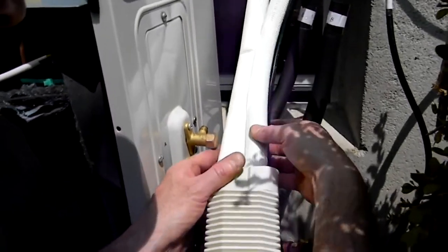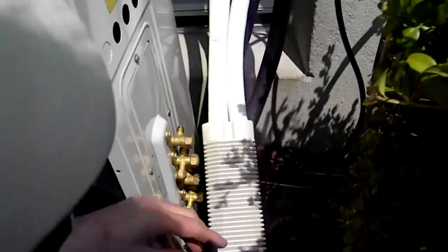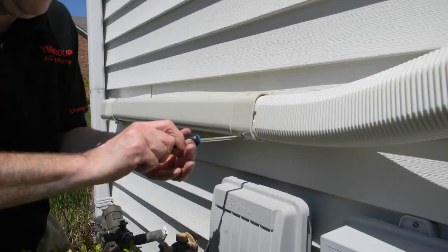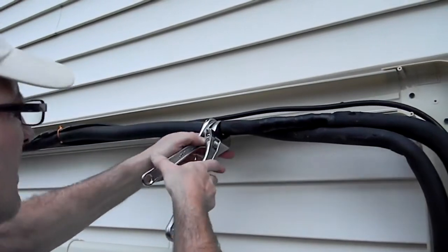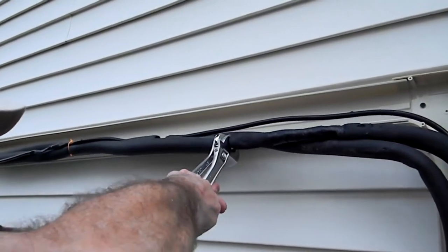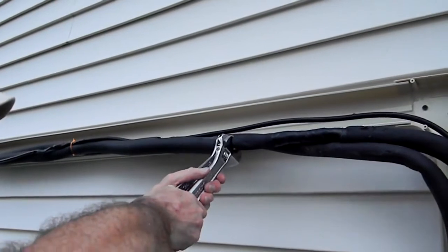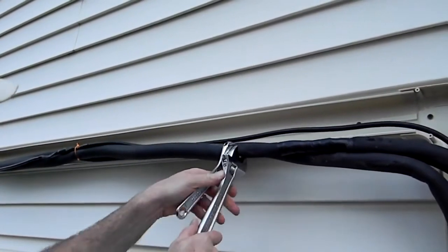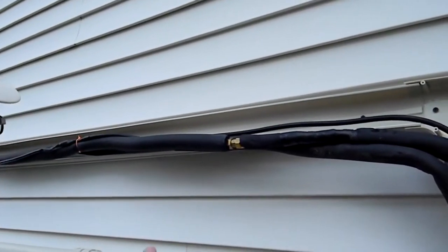Slide any flexible covering over the pipe and wire bundles before fastening them to the unit. The covered unions provide a secure and nice-looking junction between the sections. If the tubing needs to be extended, make the extensions after the backing is in place. Tighten all connections and do not enclose it until all leak check operations are performed.